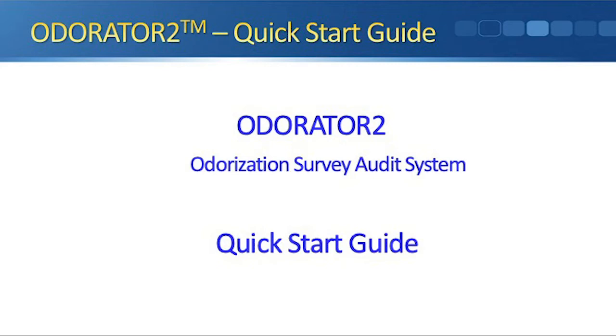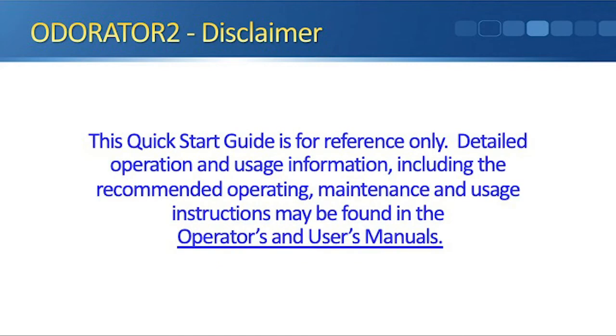So as Brian mentioned, the Odorator 2 is a survey audit system overall. I thought I would provide an overall presentation of the software, by way of a review of how a new instrument is typically brought online, put into service and commissioned to be able to take odorization test reads. So this is a quick guide, and it is just a reference during my discussion. It's by no means what has to be. It's for illustration only. The quick guide is a typical sequence, and your sequence will most likely differ.